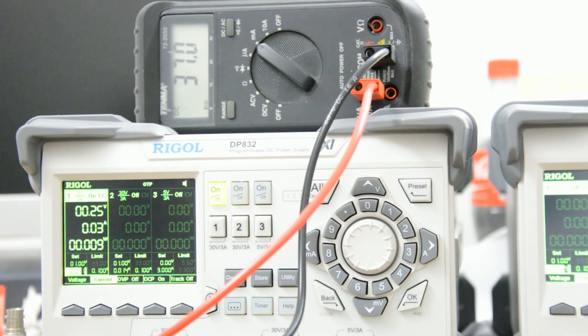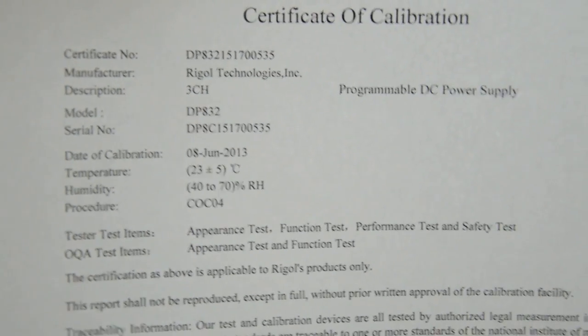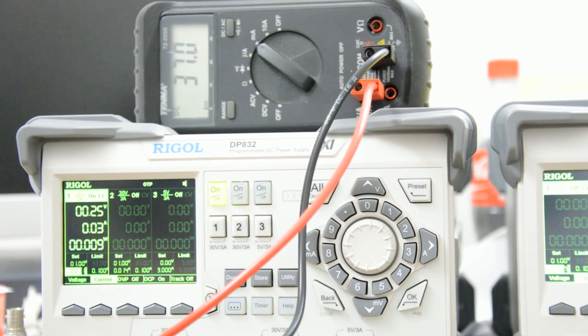So how do I go from here? When I received the unit, I also looked at the calibration certificate that was shipped with it. If you zoom into the calibration certificate, you can see that the date of calibration is June 2013 — more than a year old. I thought that was weird; I would have expected a current calibration. I asked on the EEVblog forum whether that was normal, and the replies were fairly mixed — some people said it was common, others said it was completely unacceptable.